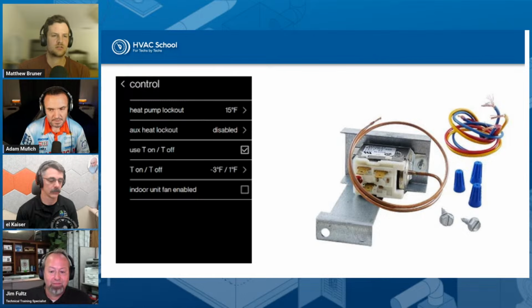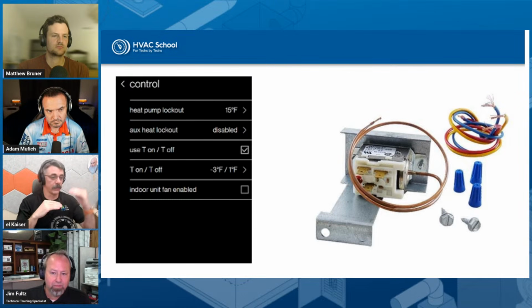And a lot of these systems, Ecobee is another one. You would have to know your balance point. Yeah, you really need to calculate your thermal balance point. Now, there are some controls out there that can do it on indoor temperature droop. When they see that compressor running 100% of the time and they don't see a rise in temperature after an hour or whatever time frame that is, then they will start cycling that electric heat, that auxiliary heat, on and off.